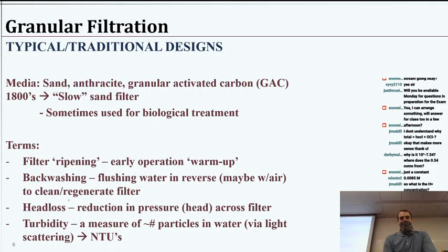So head loss is another term. This is a term we use to describe the increasing amount of pressure required to operate as the filter gets dirtier. So as you imagine, you're filling up the sand and all the grains with particles, you're blocking pores, it's requiring more pressure to push water through. Whether that's more water loaded on top to get the same flow rate coming out, or it's higher pressure in the column system. Either way, we call the pressure head, and the head loss then is that pressure drop across the filter.